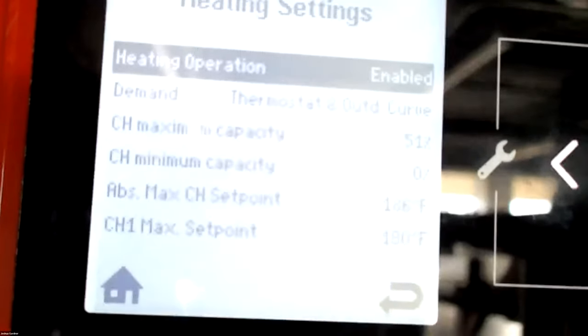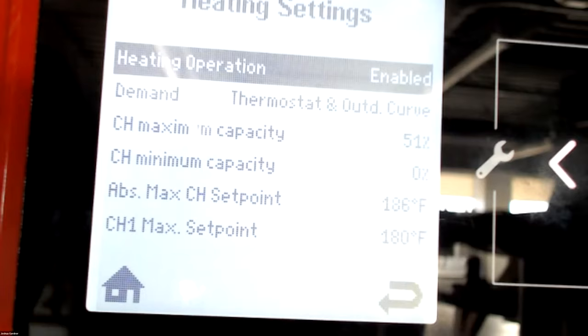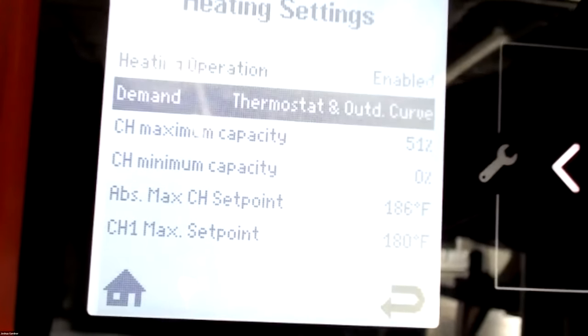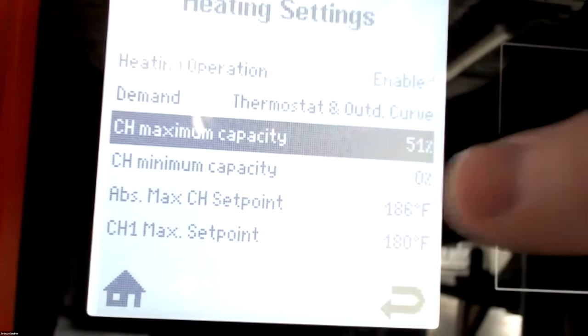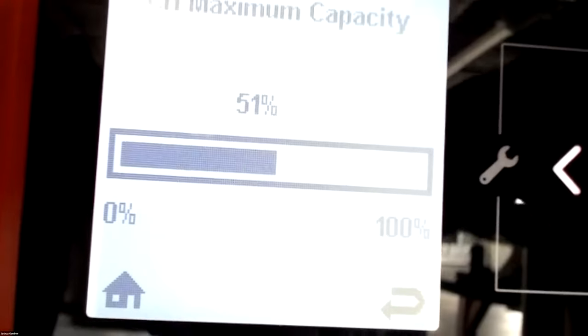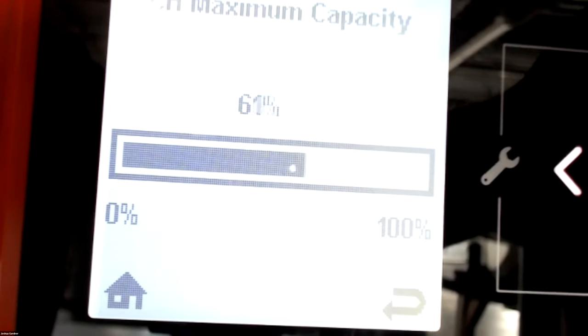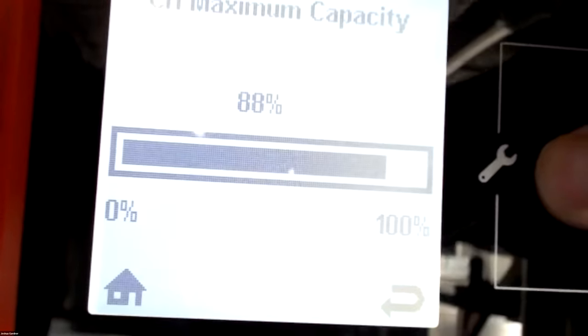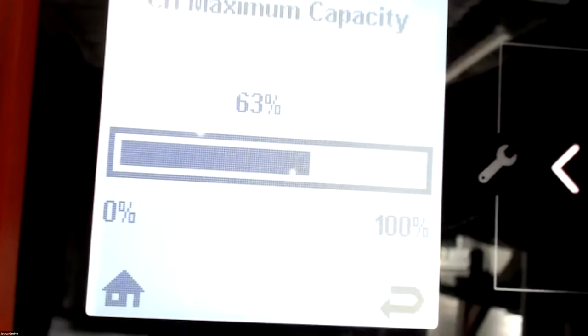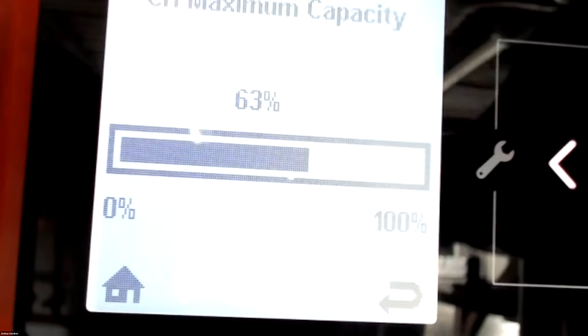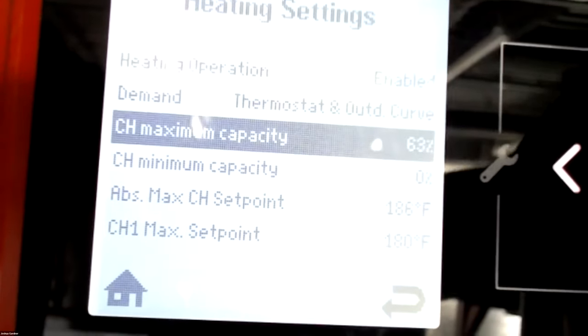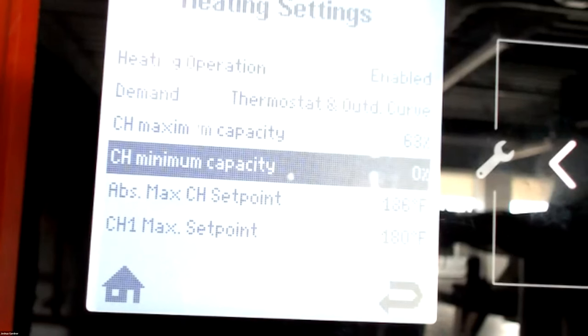So we get into the CH settings, our central heating settings. We have our information up top, thermostat, outdoor curve. We can go and adjust this stuff. CH max capacity. So this is going to be coming through from us at 100%. This is where you can derate that boiler. So if you want to drop that maximum capacity, because you don't need all 155,000 BTUs, this is where that's done. And then the minimum capacity, if for some reason you wanted to bring it up and not have it fire at a low fire rate, that's where you could adjust that.